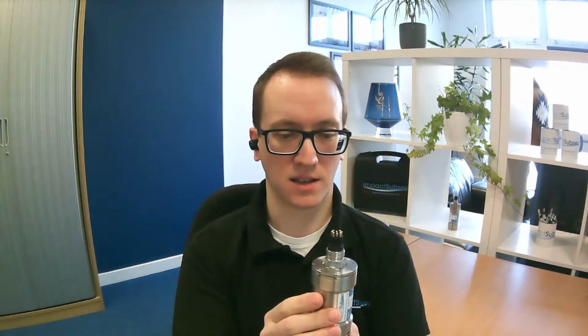So the heading is based on magnetic north. So when you first power it up, magnetometers find where north is, and the heading is aligned to that. Then the gyros and the accelerometers help stabilize that heading. So if you have a temporary magnetic interference, maybe you come up close to a pipeline, that'll affect the magnetometers, but the gyroscopes and accelerometers don't register any heading change, so they hold the original heading. If you sit there for a long time, it will slowly drift around, but you have a limited amount of protection from a temporary magnetic interferer.